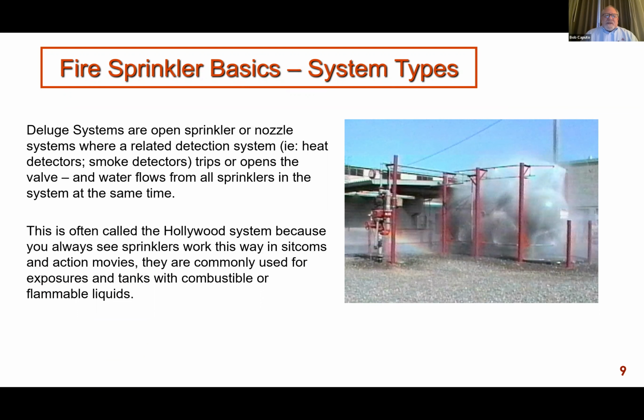Here comes my deluge system. In a deluge system, which we in the industry call a Hollywood system, because this is how Hollywood depicts fire sprinklers. Arnold Schwarzenegger lights a cigar in the elevator and all the sprinklers in the parking garage go off, which is absolutely ridiculous, by the way. But this is an example of a deluge system. In this case, the nozzles or sprinklers are all open. And when my detection system opens the valve, then all the nozzles are going to flow at one time.